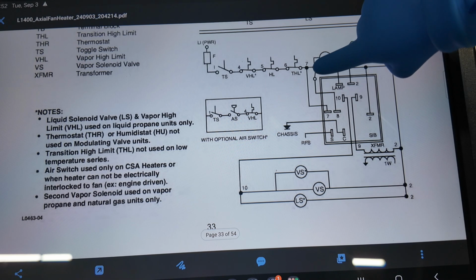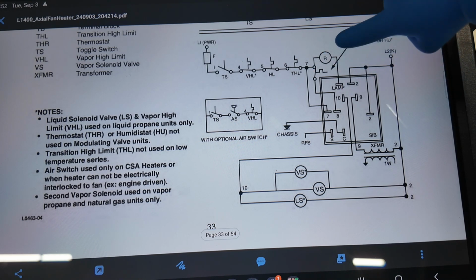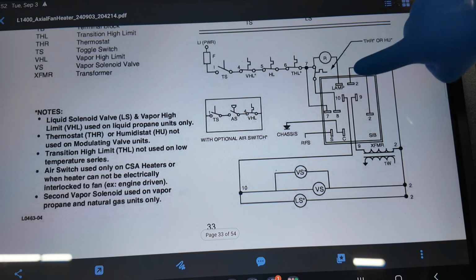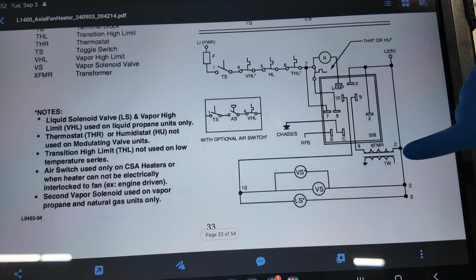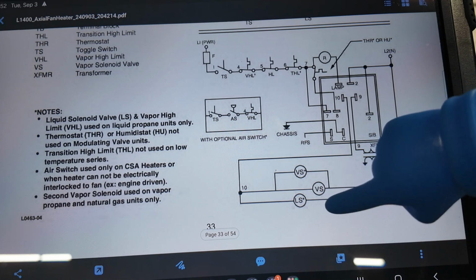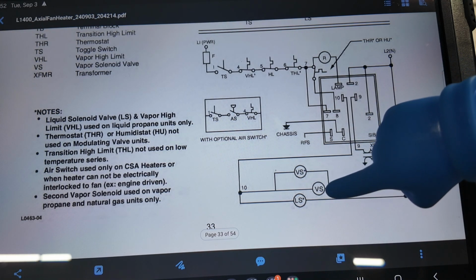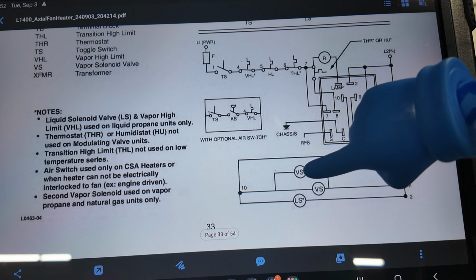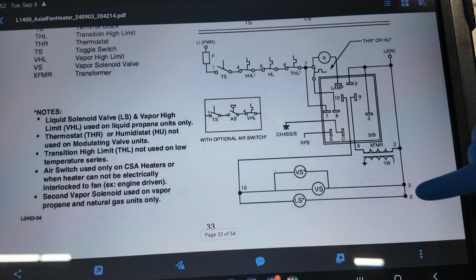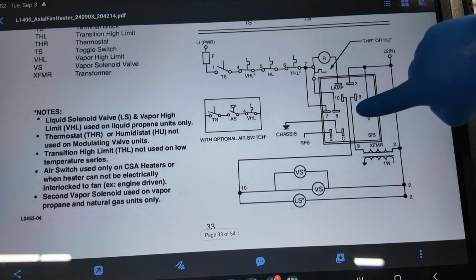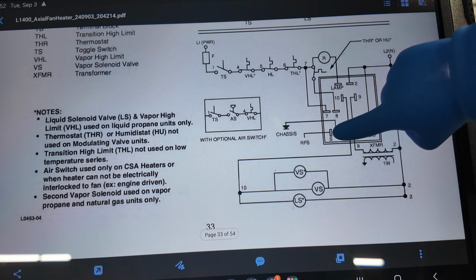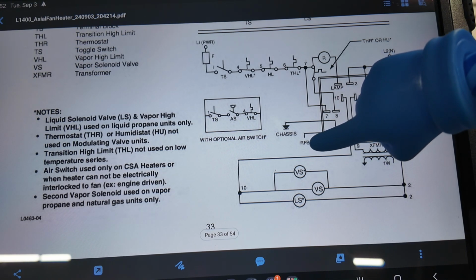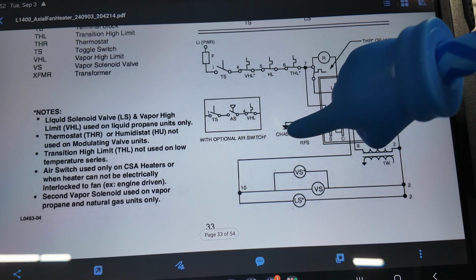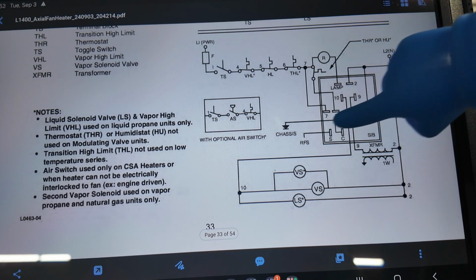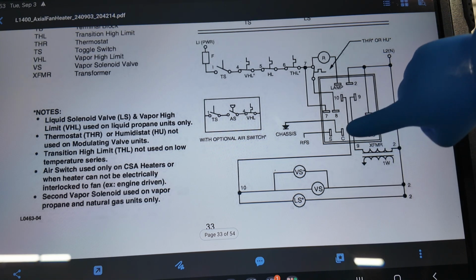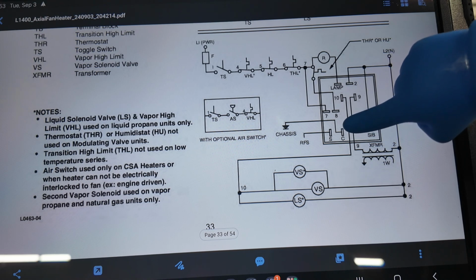Then the lamp would connect to terminal 7 and the lamp terminal, and your number 2 terminals would both connect to neutral and to the one side of your gas valves, your vapor solenoids, possibly a second if you have a high-low, your liquid solenoid, the one side of your spark transformer. Then you have your sensor, goes to your flame sensor in the flame. Your C goes to the chassis, to the frame. That's your common, your ground, burner ground, it's called on some burner control units.